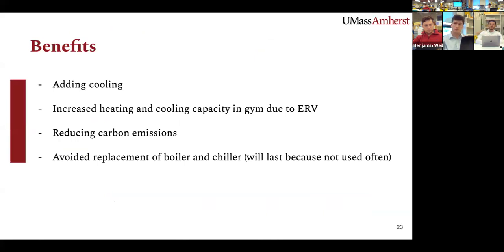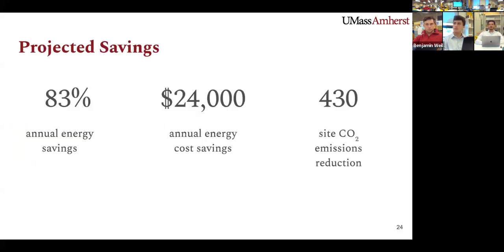If you guys adopt this plan, some of the benefits would include adding cooling throughout the entire school, reducing carbon emissions, increasing heating and cooling capacity in the gym. And we know that this was one of the biggest issues that you guys had. And we think that with the addition of installing ERVs and circulating fresh air, you'll have plenty of capacity, which will help fix that issue. And then finally, you guys would avoid replacement of the boiler, since the boiler won't be running on as many cycles, it will last longer.